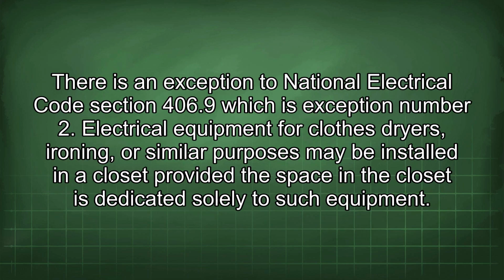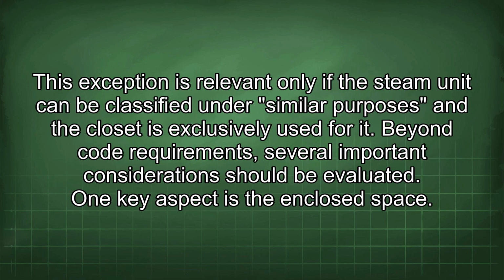There is an exception to National Electrical Code section 406.9, which is exception number 2. Electrical equipment for clothes dryers, ironing, or similar purposes may be installed in a closet provided the space in the closet is dedicated solely to such equipment. This exception is relevant only if the steam unit can be classified under similar purposes and the closet is exclusively used for it. Beyond code requirements, several important considerations should be evaluated.